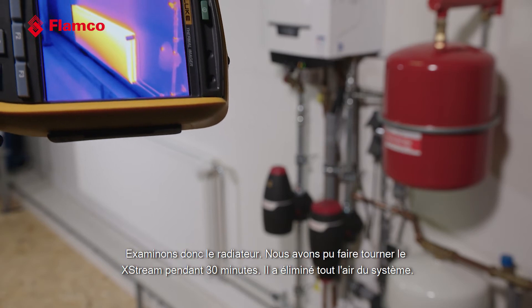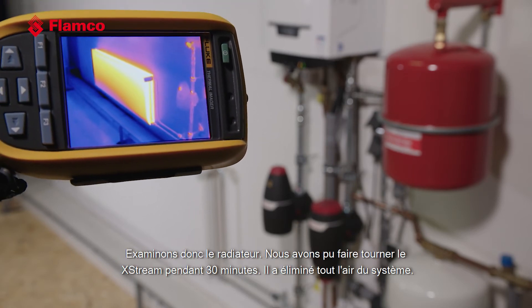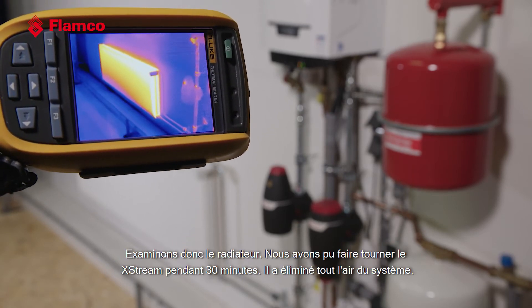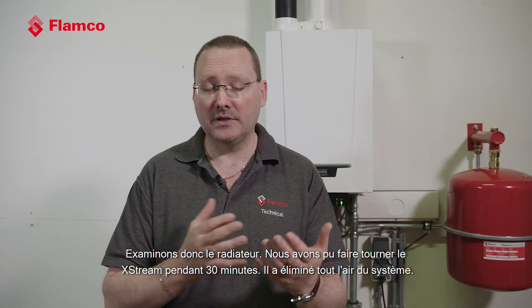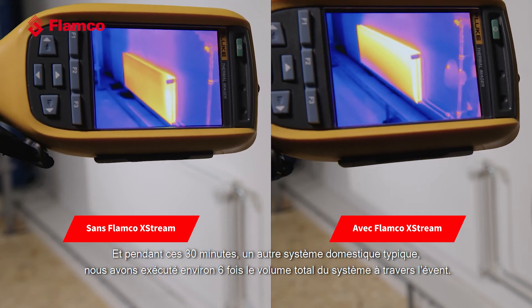Let's have a look at the radiator. The radiator now — we've been able to run the XStream for 30 minutes — has removed all of the air in the system. In that 30 minutes on a typical domestic system, we've run about six times the total system volume through the vent.